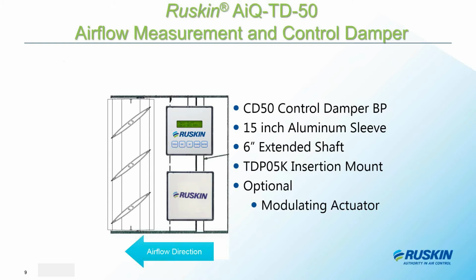The AIQ TD50, as I mentioned, is the first in this series. As we roll it out, it will be available in the future with any Ruskin control damper similarly configured. Our next product, for example, will be the AIQ TD60 in a galvanized steel sleeve. Again, this product is made in Parsons, Kansas, and air measurement is in close proximity with the damper. The damper is always a parallel blade damper for air measurement applications.